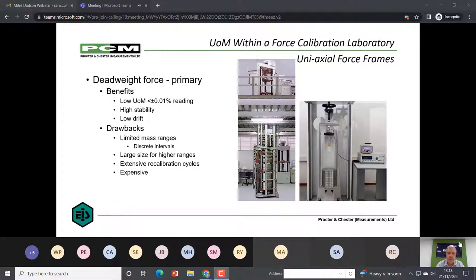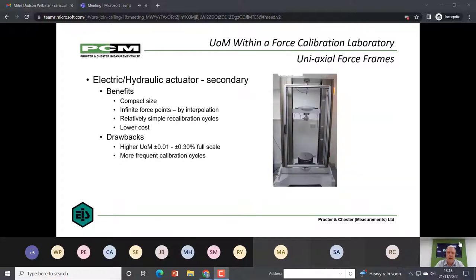So a lot of facilities will have an electro-hydraulic actuator as a secondary calibration device, again uniaxial. Again, this is our 10 kilonewton frame. The benefit of this is it's a very compact size. By interpolation, we can have infinite force points, and relatively simple recalibration cycles, because it's almost modular in construction. The instrumentation can come out and be calibrated independently. They tend to be significantly lower cost as well.